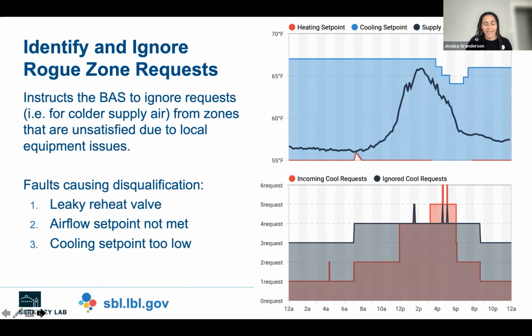Now, this was implemented in tandem with routines to ignore or suppress cooling requests from rogue zones. So those are actually identified through some of the faults that we know we can detect with these types of technologies. So if we know that the zone has a leaking reheat valve, or the airflow set point's not being met, or the cooling set point is far too low, then we're just going to discount those cooling requests. And that's actually shown on the bottom plot in the darker black shading. So those are the zones whose requests have been discounted.